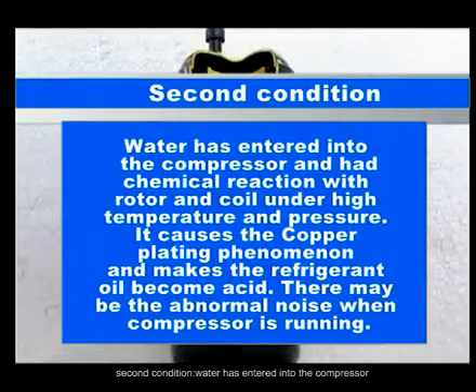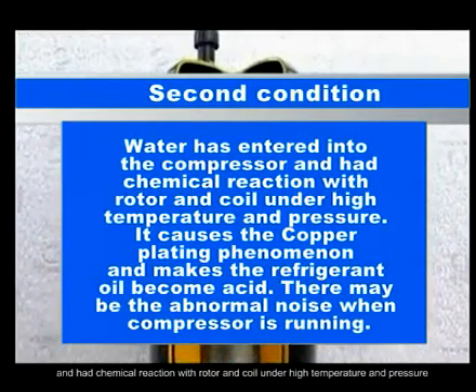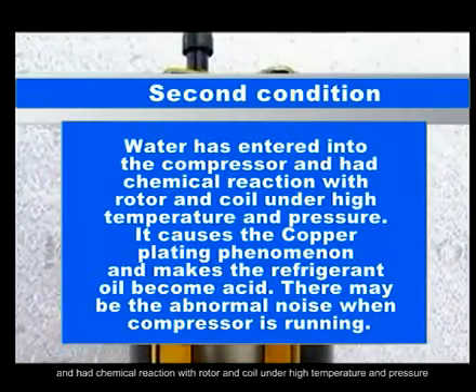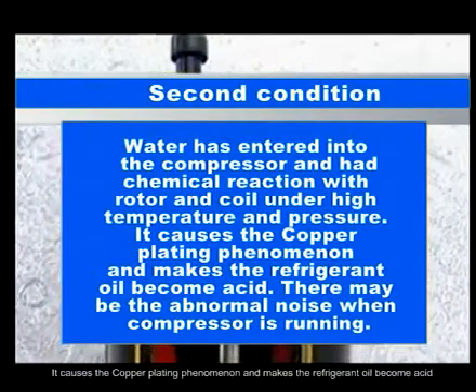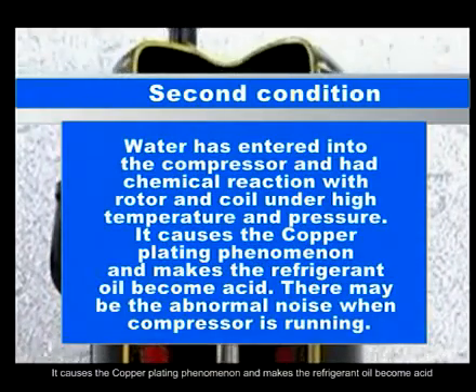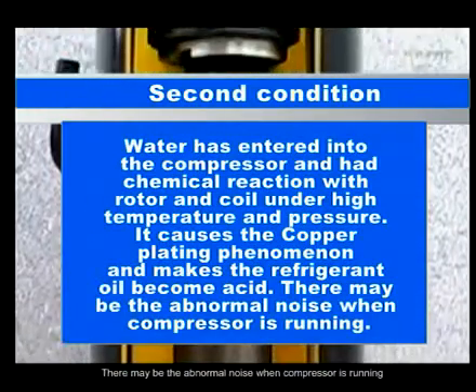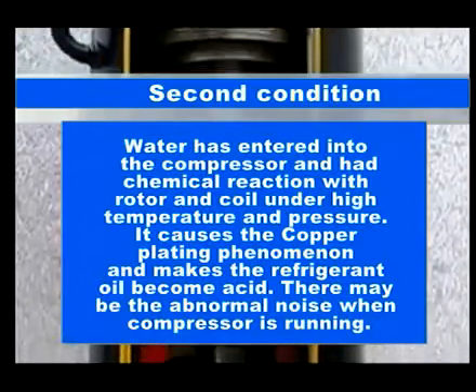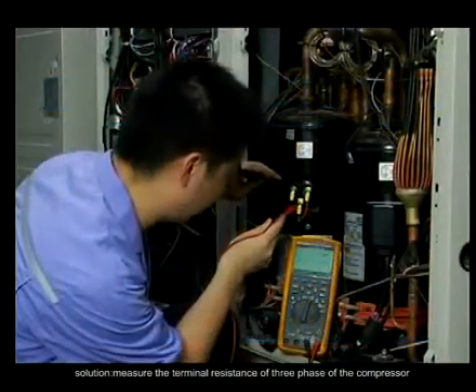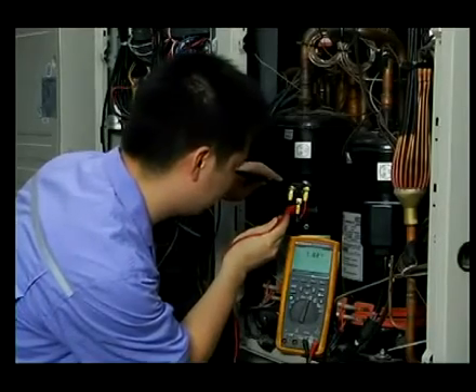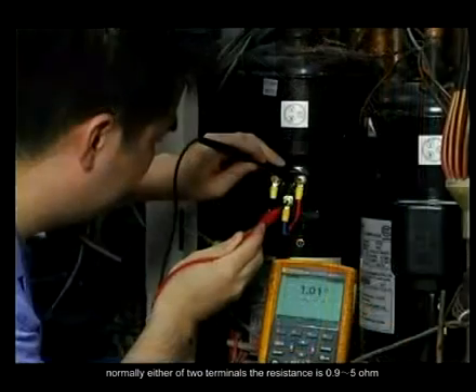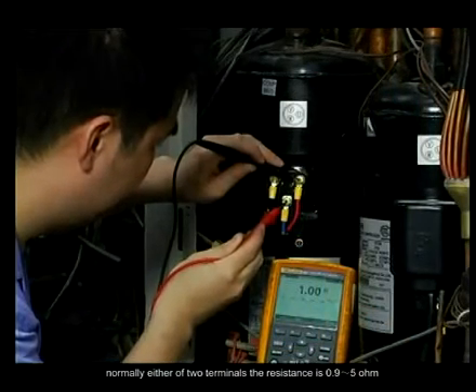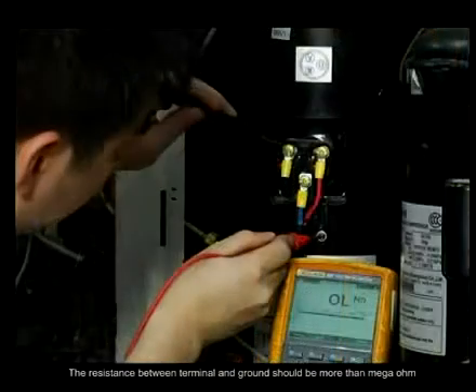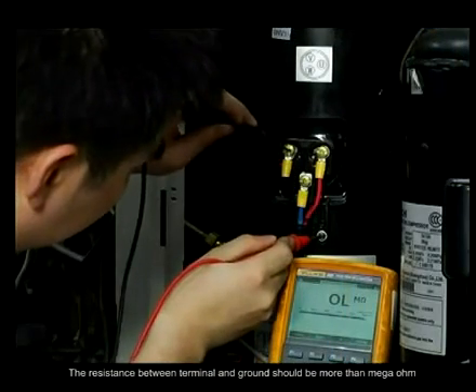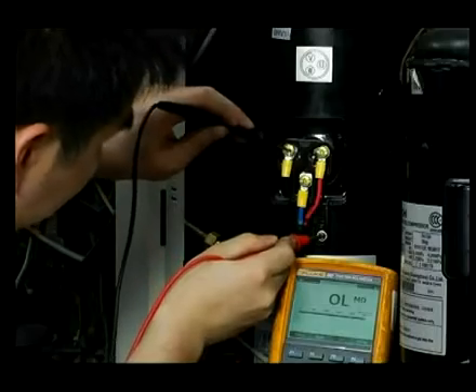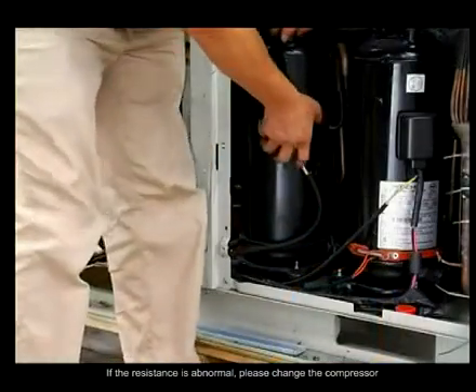Second condition. Water has entered the compressor and had a chemical reaction with the rotor and coil under high temperature and pressure. It causes the copper plating phenomenon and makes the refrigerant oil become acid. There may be abnormal noise when the compressor is running. Solution. Measure the terminal resistance of the 3 phases of the compressor. Normally between either 2 terminals the resistance is 0.9 to 5 ohm. The resistance between terminal and ground should be more than mega ohm. That means the compressor is normal. If the resistance is abnormal, please change the compressor.